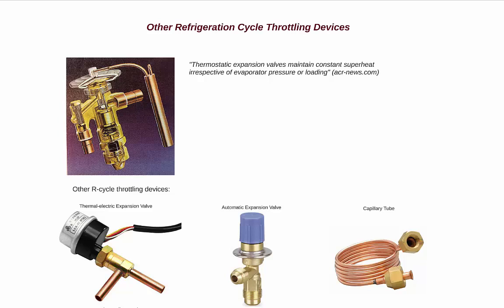load. However, the sensing bulb thermostatic expansion valve is only one of many throttling devices used in the refrigeration cycle. The thermoelectric expansion valve, automatic expansion valve, and capillary tube are all examples of other devices employed. Discussing all of these is outside the scope of this course, but we have presented one of the more common to give you a better understanding of the internal controls. There you have it. You now understand the basics of the refrigeration cycle, as well as how the thermostatic expansion valve modulates flow rate to respond to load.